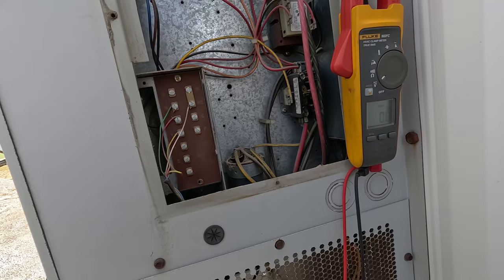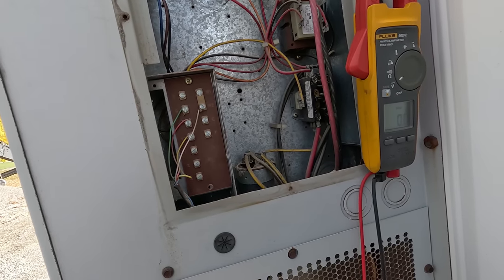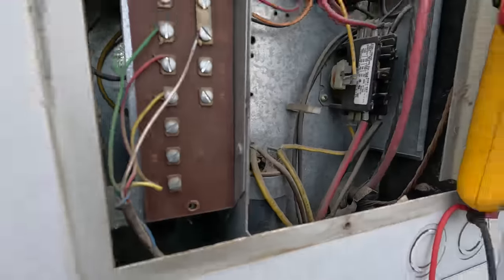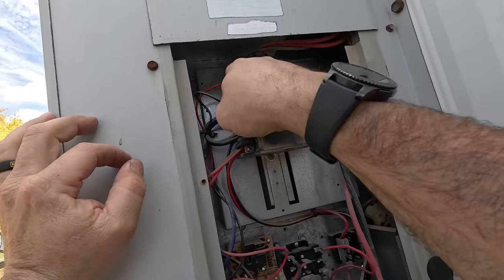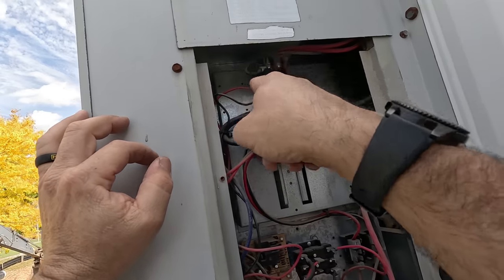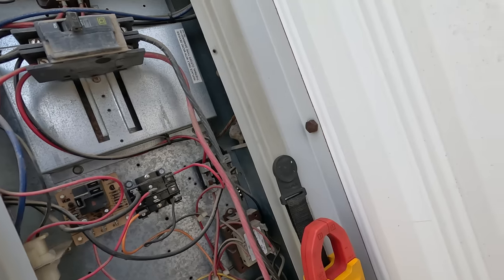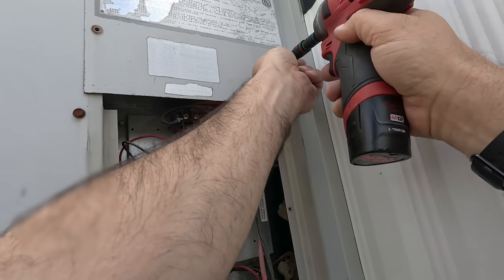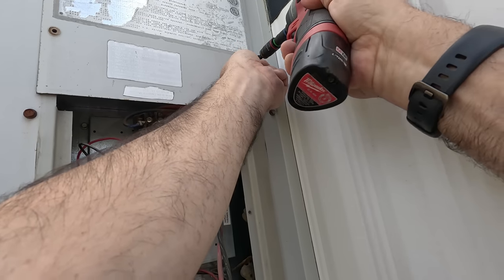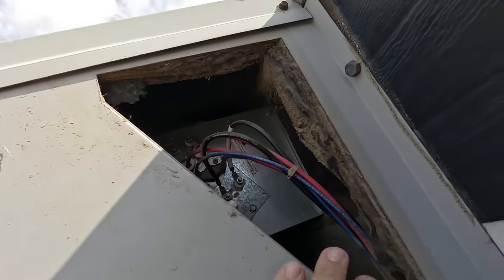I would speculate that we have a low voltage wire that got tied in with - yeah, I think I can almost already see it. Let's go up here to the top. Notice this big heavy gauge wire that's on the low voltage terminal there. I would say somebody didn't know what they were doing and wired it up like that. That's just a guess. Oh, there are your electric strips. Looking up here, you've got two electric strips.